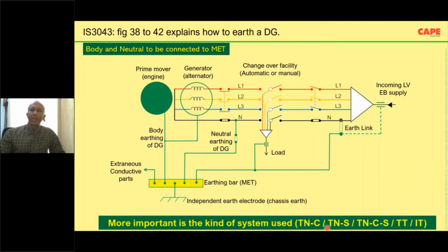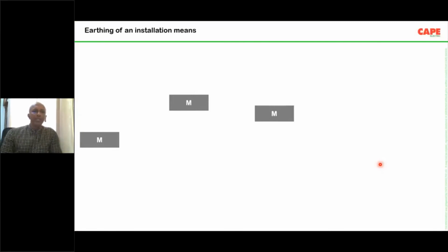There are earthing systems called TNC, TNS, TNCS, TT, IT. These are the types of wirings which you are supposed to follow, and this is much more important than the earth pit. Earthing of an installation: what do we mean by earthing? It means, number one, you have the exposed conductive part. Imagine these are the metal body of current carrying equipment, such as panel board, such as electrical apparatus, such as UPS, such as motor, and so on.